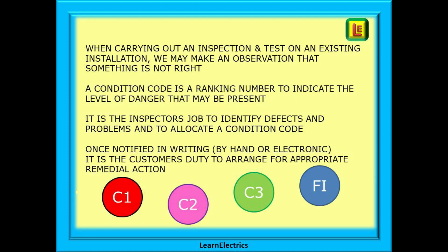Let's establish a starting point. When carrying out an inspection and test on an existing installation, we may make an observation that something is not right. A condition code is a ranking number to indicate the level of danger that may be present with that particular observation. It is the inspector's job to identify defects and problems and to allocate a condition code. It is not the inspector's job to repair it — inspecting is not repairing, although you may be asked to quote separately for the repairs.